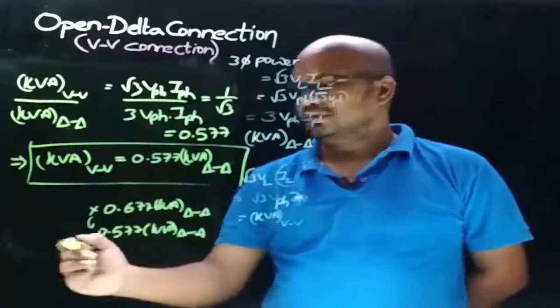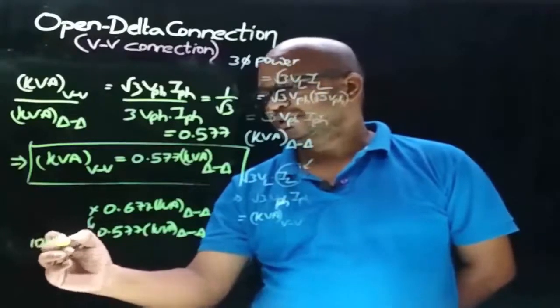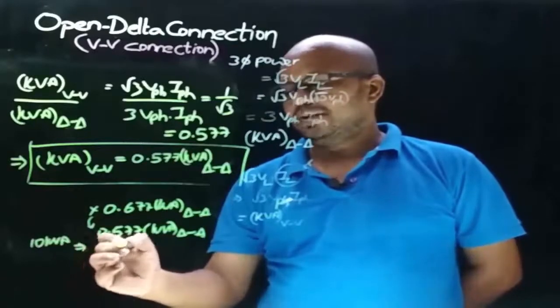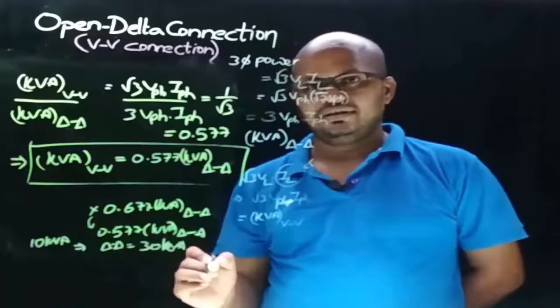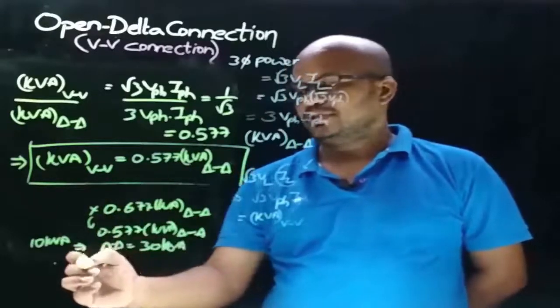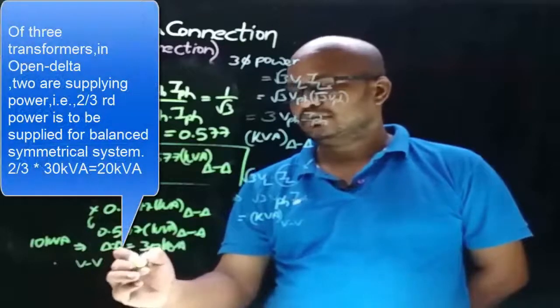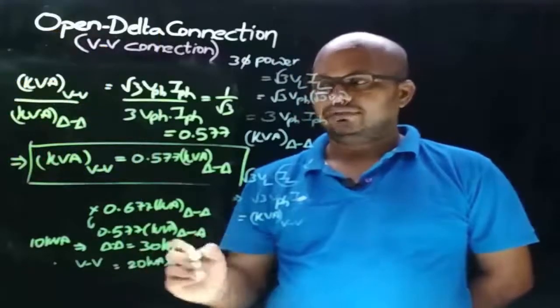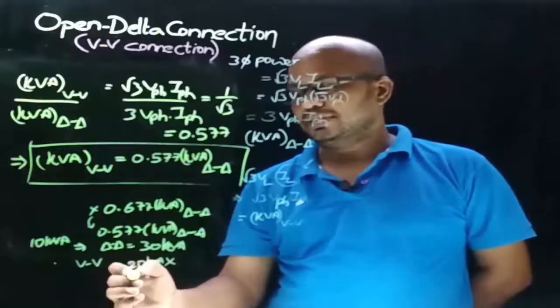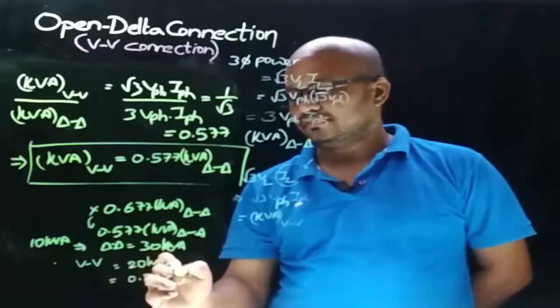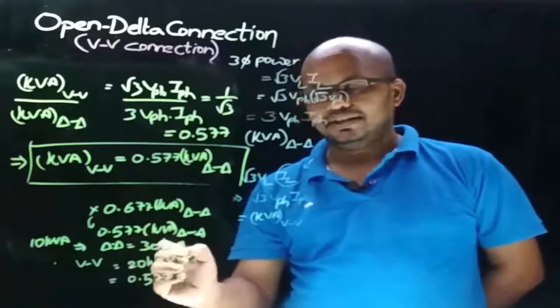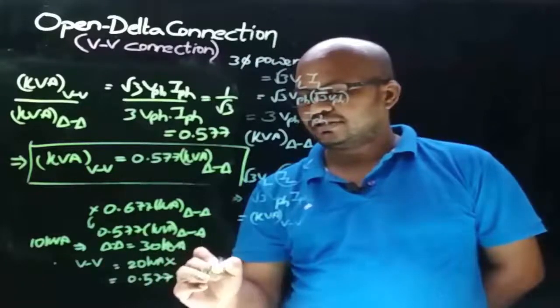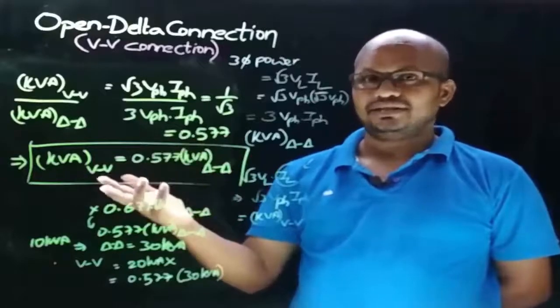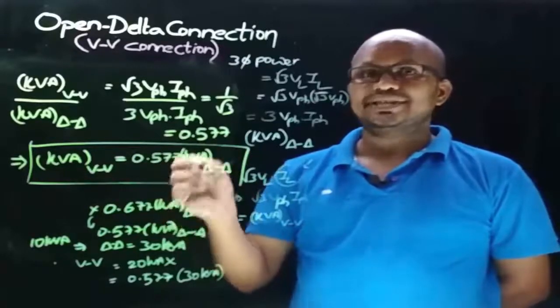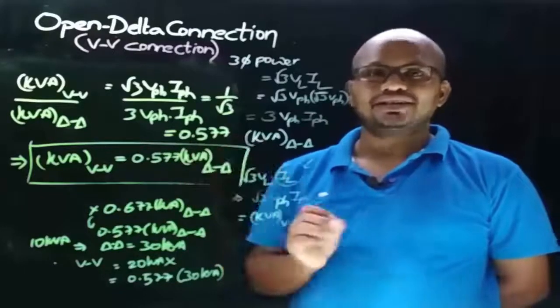Let's understand this with an example. Let us consider the rating of each transformer to be 10 kVA, meaning the power delivered by delta-delta connection is 30 kVA. And when one of the transformers fails, what we generally think is that the power delivered by open delta connection must be 20 kVA, because here 2 transformers are involved. But this is not true. With open delta connection, the power transferred will be 0.577 times the rating of delta-delta connection, that is 30 kVA. Therefore, with open delta connection, we can say that the power delivered to the load is 57.7% of the delta-delta connection rating.